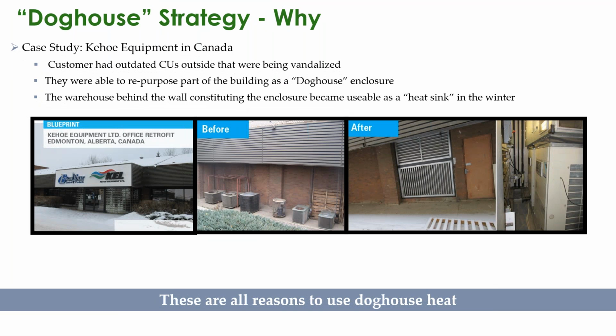For one instance, this is a case study in Canada where the customer had outdated condensing units that were being vandalized outside their building. They had an empty mechanical room inside the building that was surrounded by a conditioned, heated warehouse, and this vacant mechanical room was on the outside wall. They were able to utilize that warehouse as a heat sink and implement dampers to do a doghouse, to put that equipment on the outside wall, use that space again, and reduce their overall install cost because it was already very easy to develop.